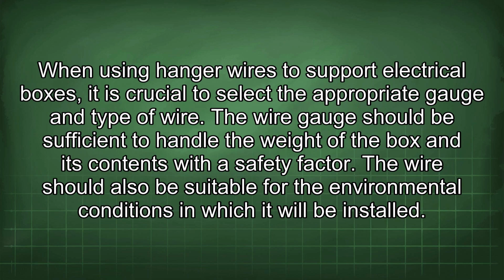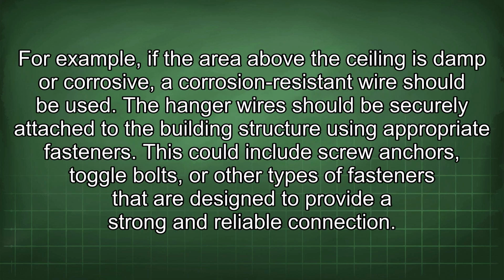When using hanger wires to support electrical boxes, it is crucial to select the appropriate gauge and type of wire. The wire gauge should be sufficient to handle the weight of the box and its contents with a safety factor. The wire should also be suitable for the environmental conditions in which it will be installed. For example, if the area above the ceiling is damp or corrosive, a corrosion-resistant wire should be used.